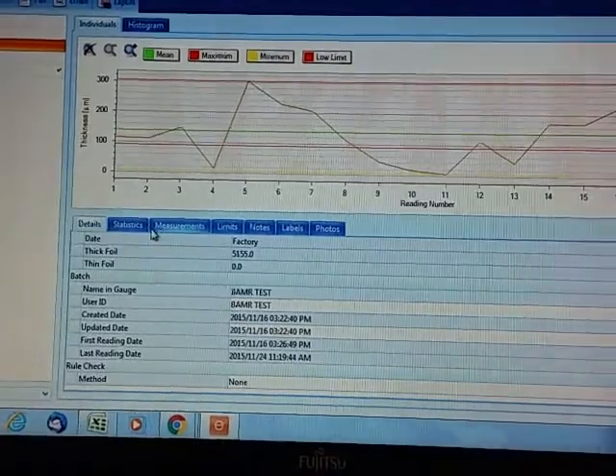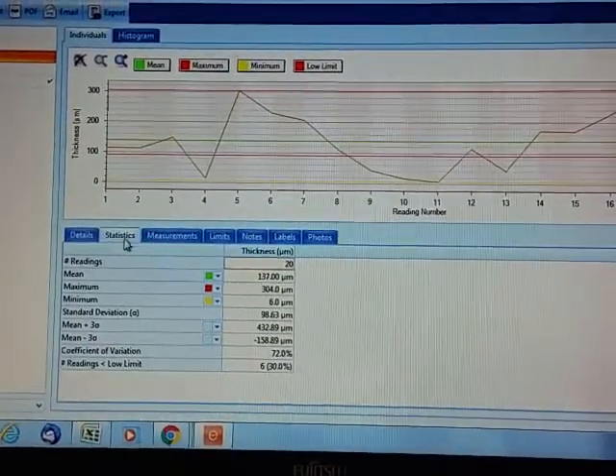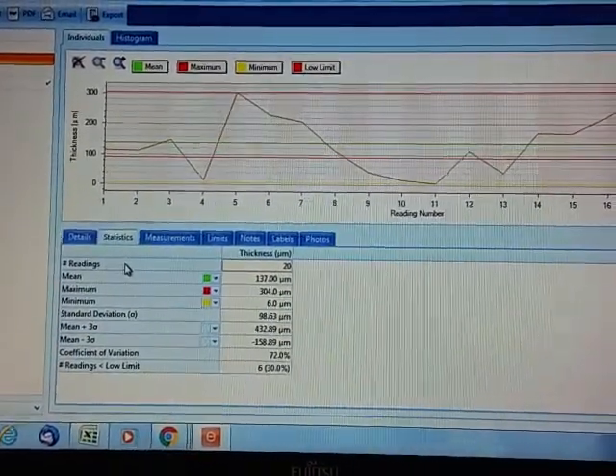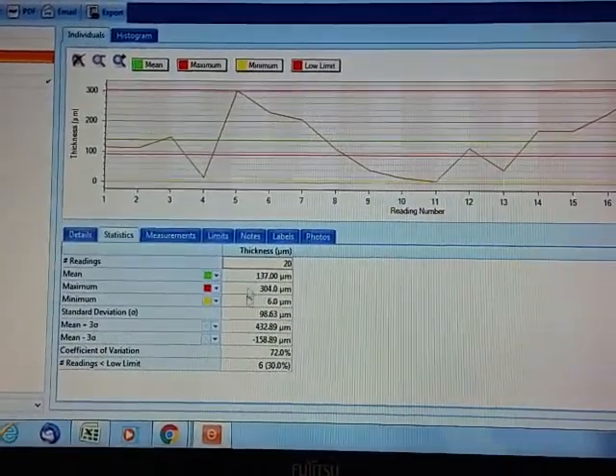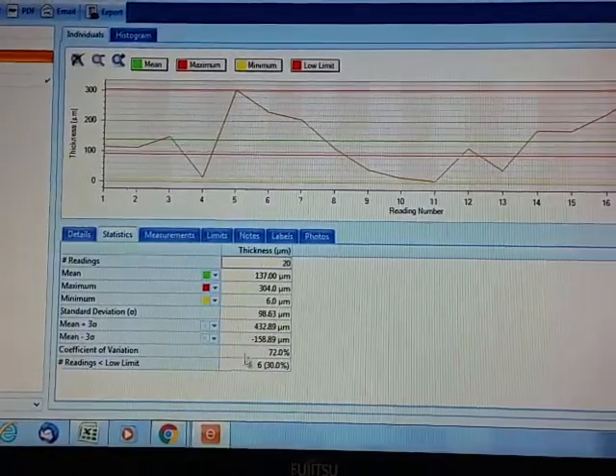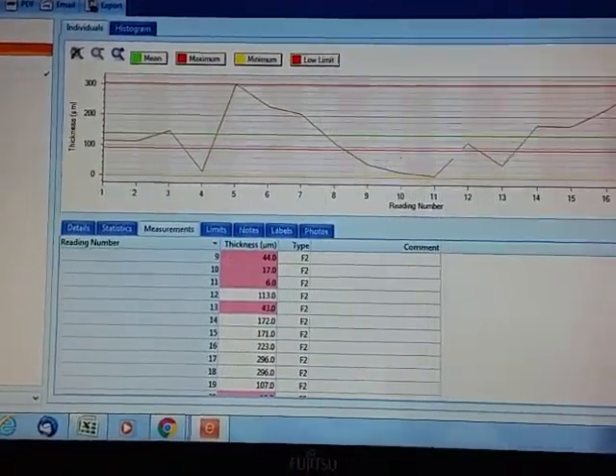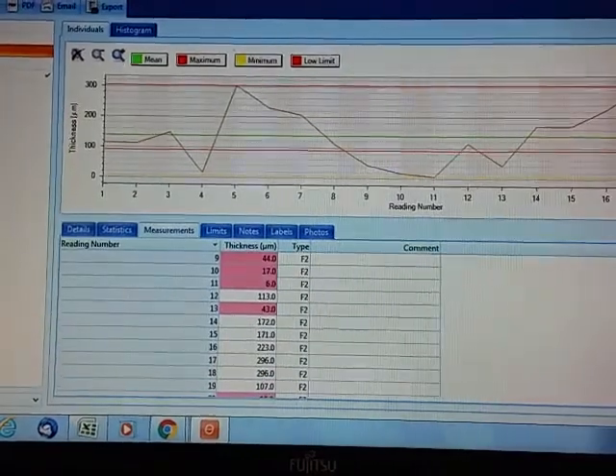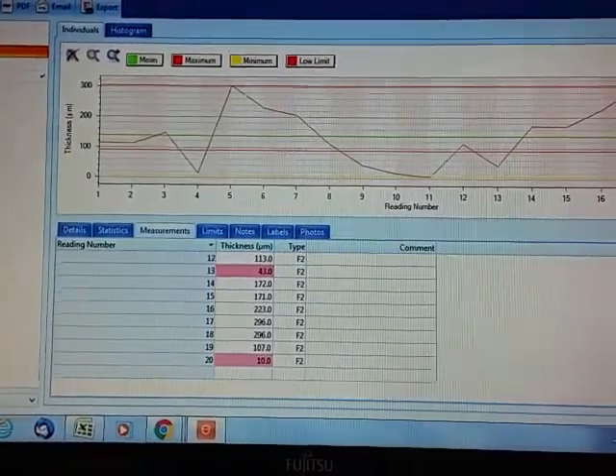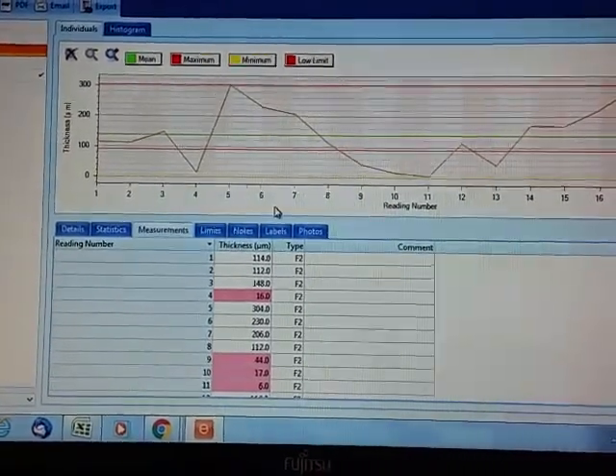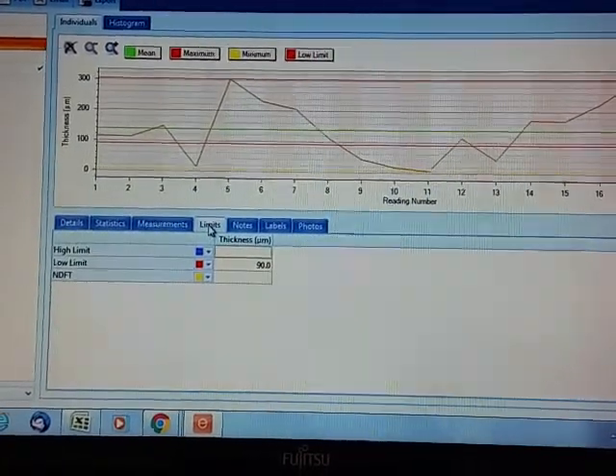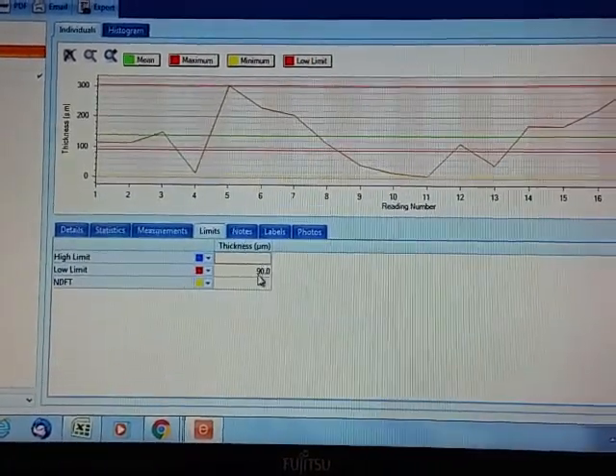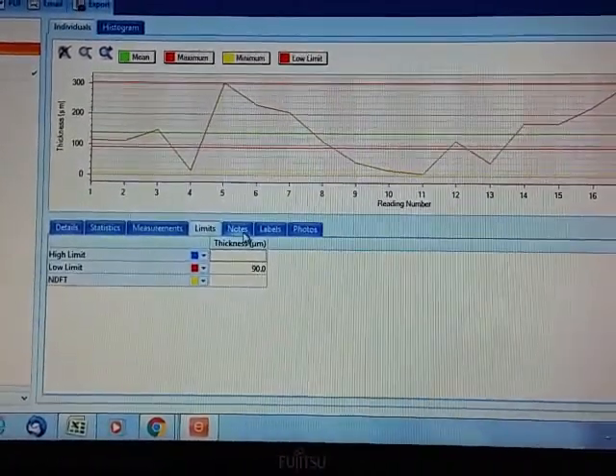Under statistics, we have the number of readings, the mean, max, minimum, etc. Under measurements, we've got our 20 readings with the ones that are out of limit in red. The limits that we set on the gauge are here - the limit is 90.